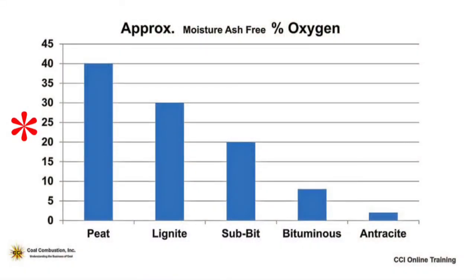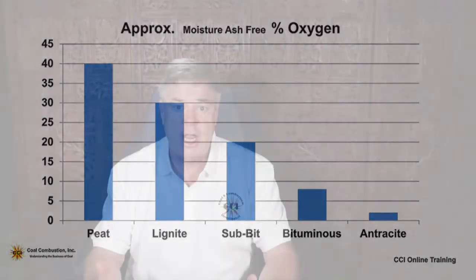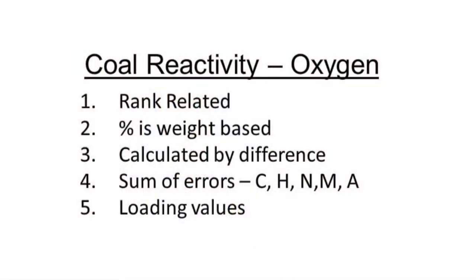One way another scientist told me to think about it: if a coal has 20% moisture-ash-free oxygen in it, and air is 21% oxygen, that coal actually has its own air associated with it. So when you see moisture-ash-free oxygen values in the 20–30% range, these coals essentially contain their own oxygen and don't need a lot of outside air to self-heat. The oxygen content from the laboratory is a weight percentage basis, not correlated to calorific value, and it's calculated by difference — so like fixed carbon, it carries the sum of the errors of moisture, ash, sulfur, carbon, hydrogen, and nitrogen measurements.